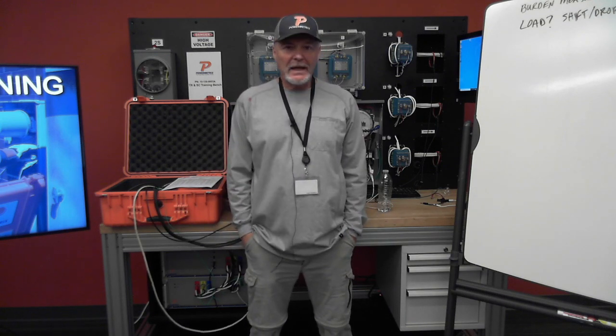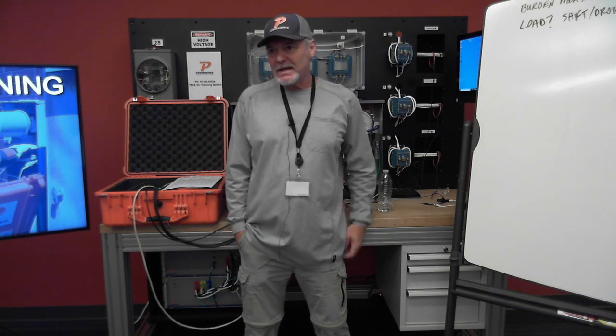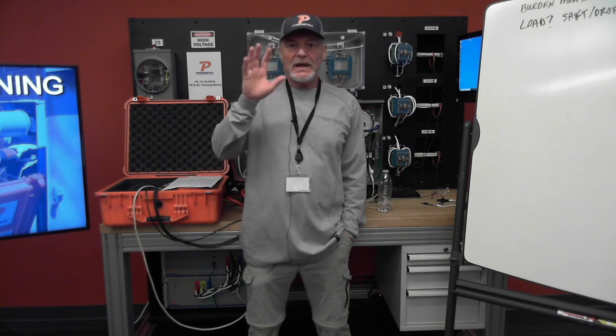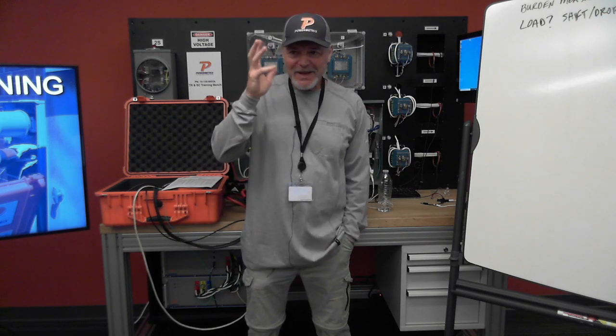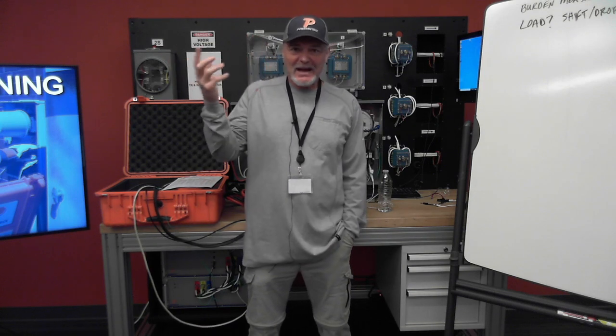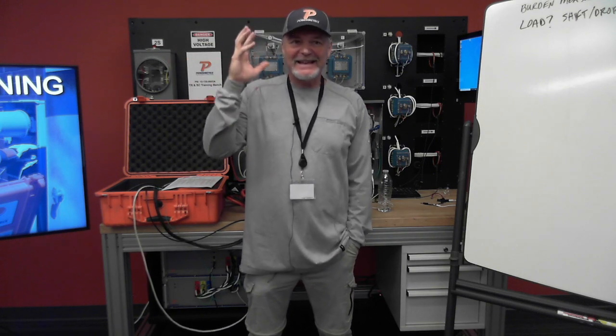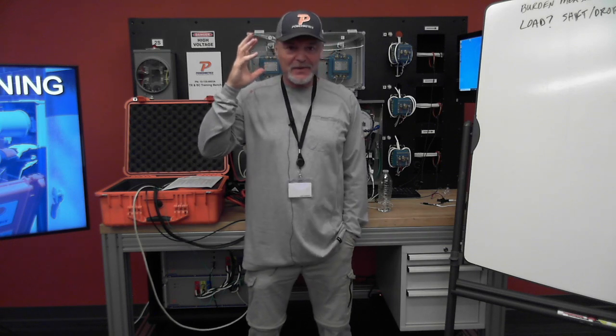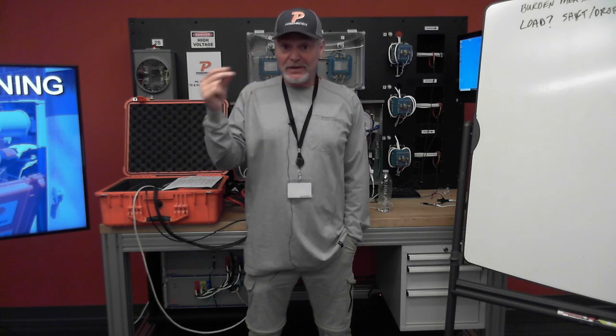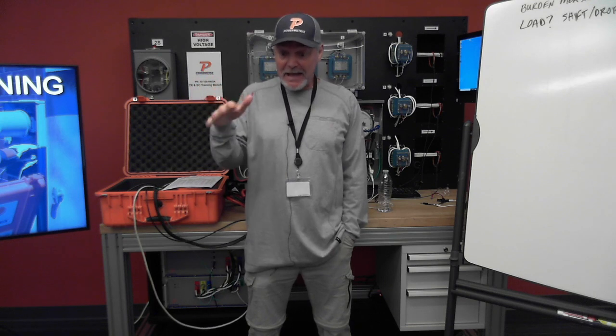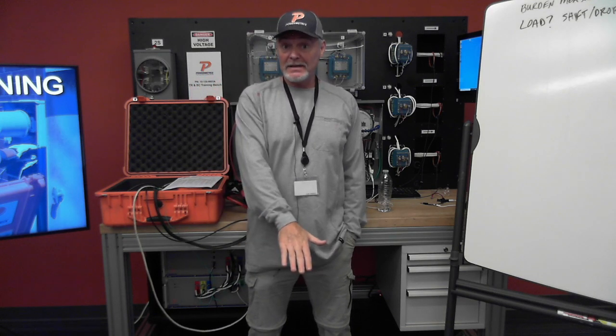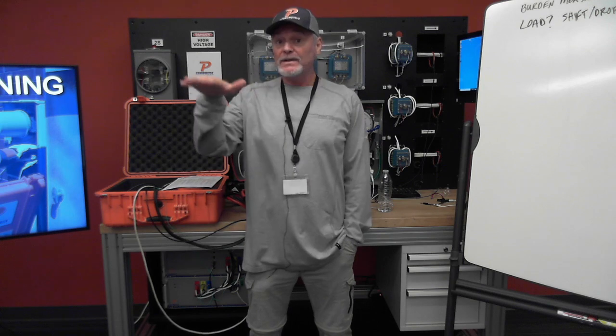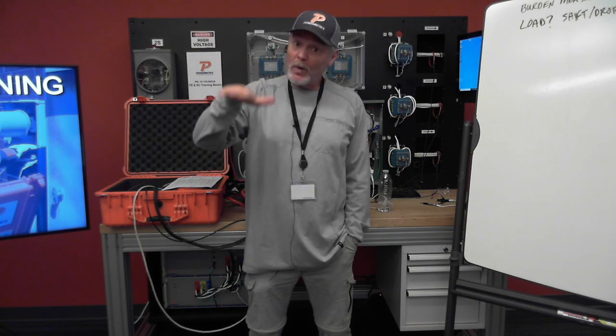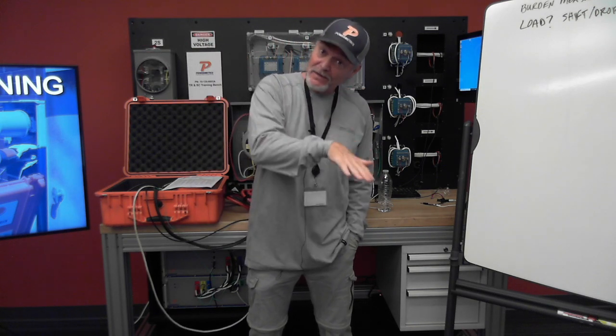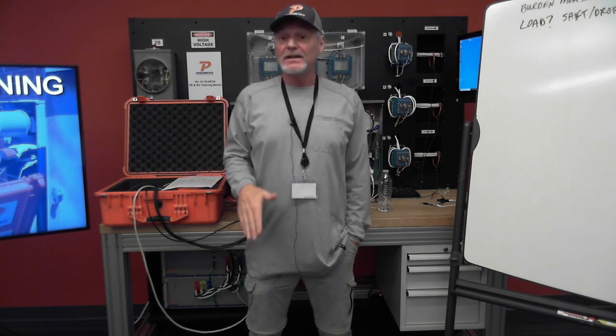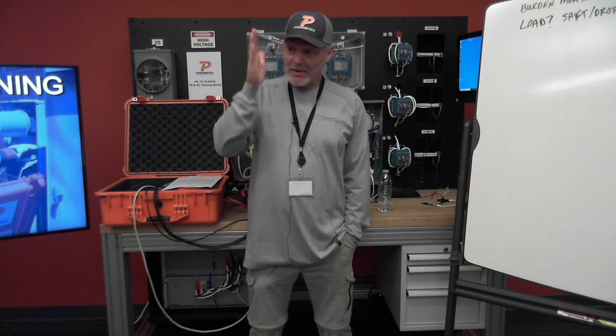One thing I noticed, and I made a little note to myself, was that I like the way to always be cognizant of that load. You get guys like Jonathan and Browland, those meter techs out there doing this every day, all day - you learn to look for that load. If all of a sudden I could get a dip in load and I could get a bad test, and then the load comes back up. So always be cognizant of your load, because if you don't have enough load, it's going to be difficult to test those CTs.